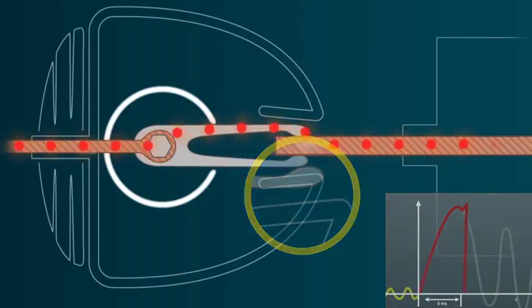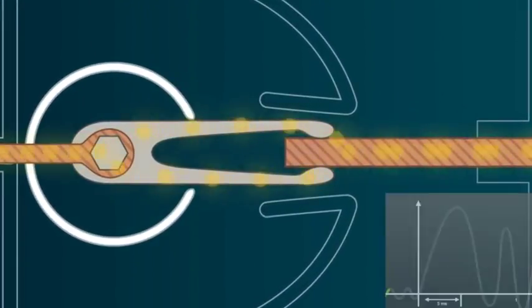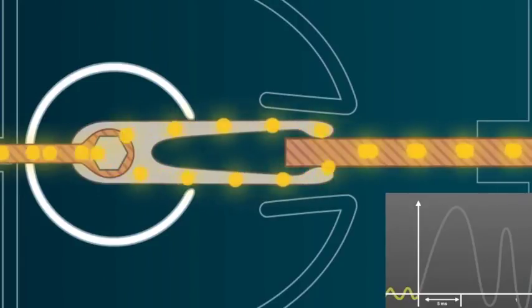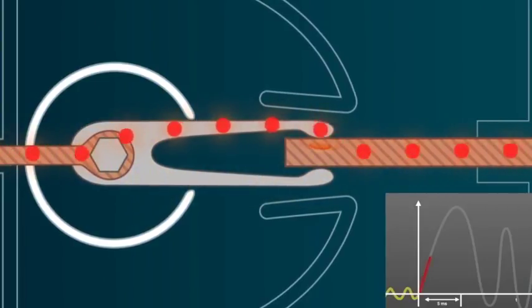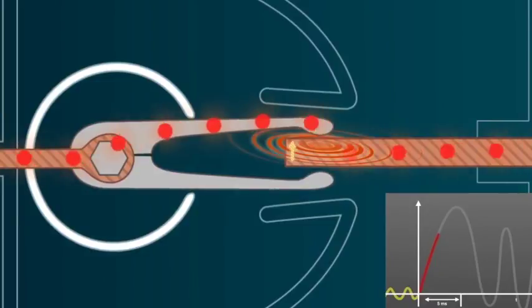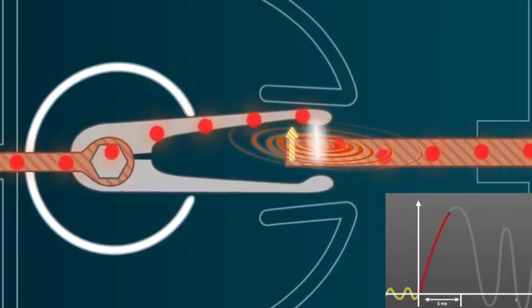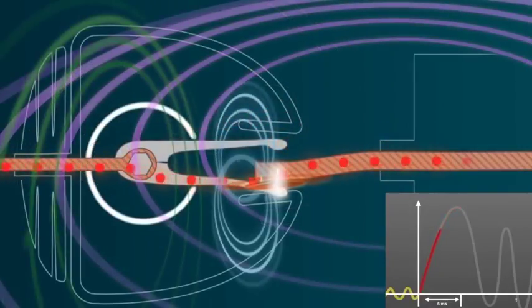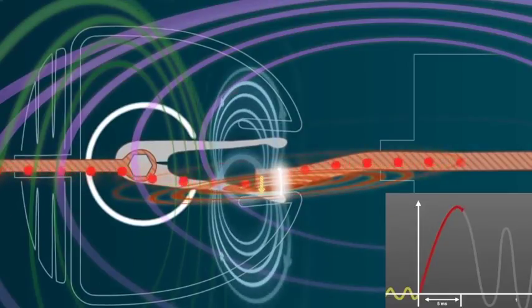The repulsive contact force caused by electromagnetic constriction will finally become the most critical effect, pushing the contacts away. This causes a flashing arc which could eventually result in greater damage should ionized gases short circuit two phases.